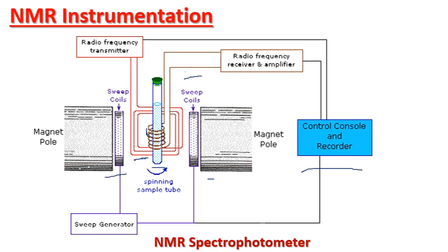An NMR spectrum is acquired by varying or sweeping the magnetic field over a small range, and for sweeping this magnetic field we are using these sweeping coils, while observing the signal from the sample. An equally effective technique is to vary the frequency of the radio frequency radiation while holding the external field constant. So this is the actual NMR CW method spectrophotometer.